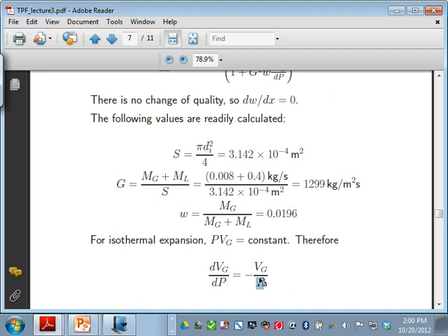It's a vertical pipe. The pressure at the end of the pipe is 100 kPa, but the pressure at the bottom of the pipe is 107 kPa, according to our estimate. It's higher. So by right, putting one value here is not so correct.